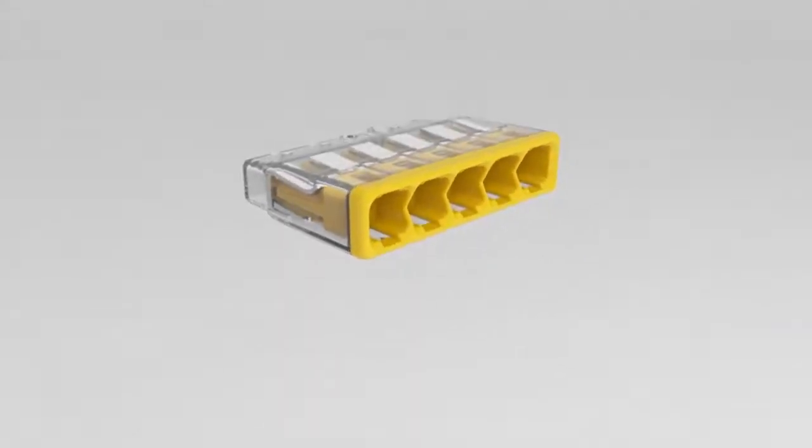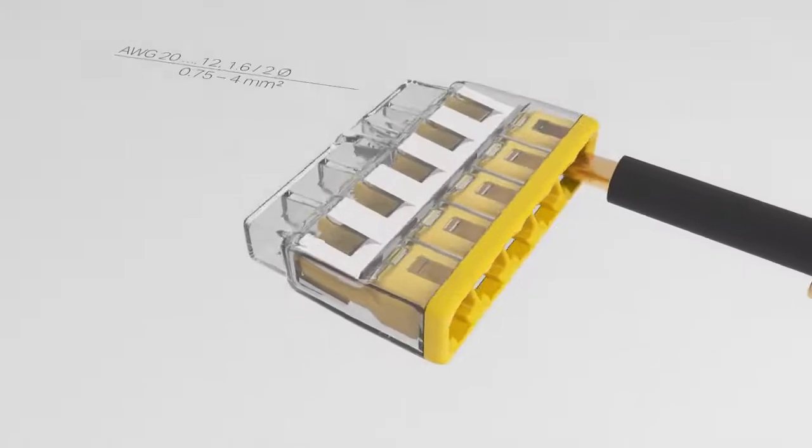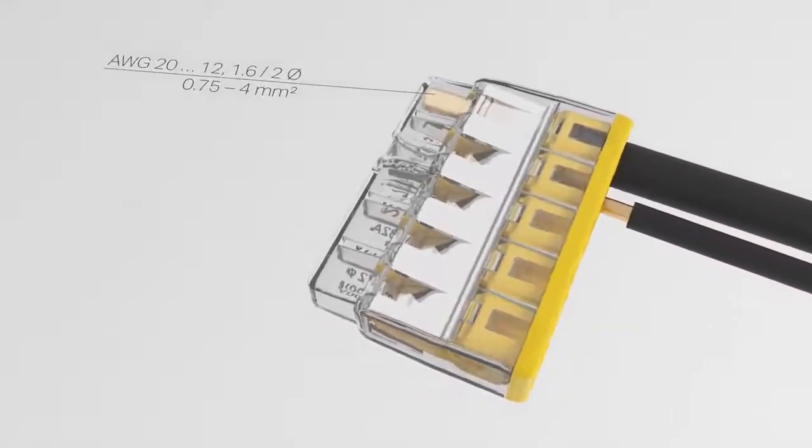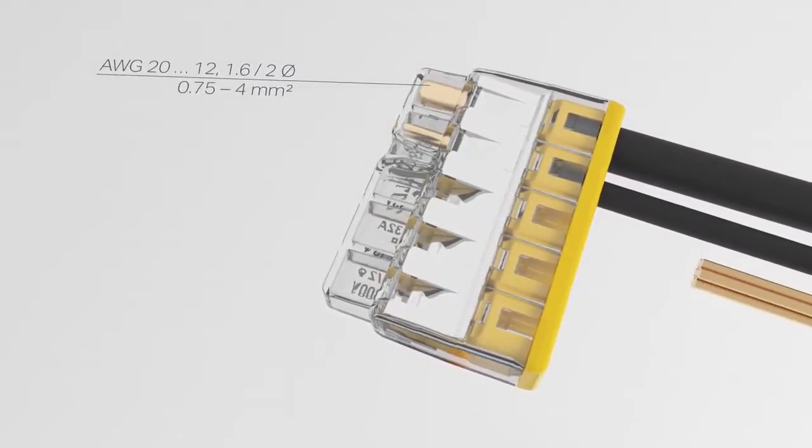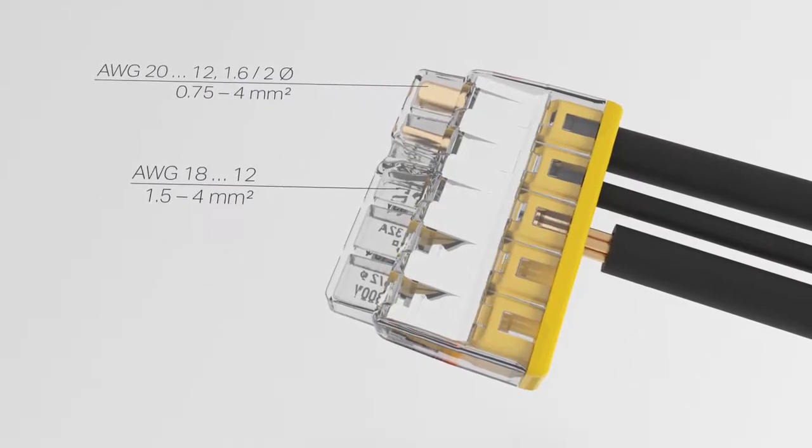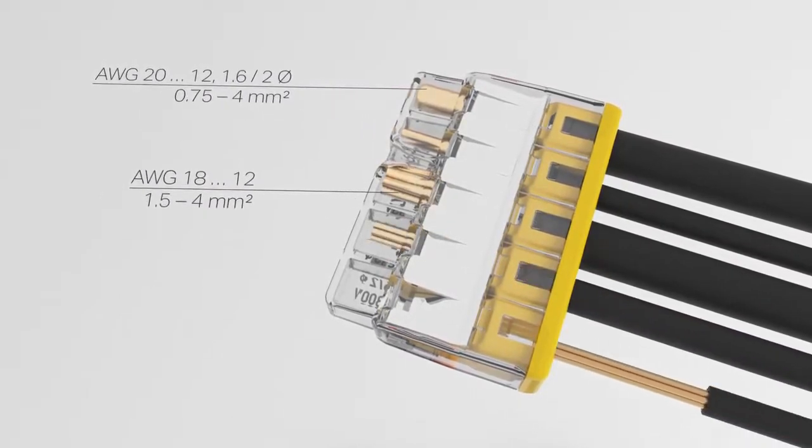Solid conductors with cross sections ranging from 0.75 square millimeters to four square millimeters and stranded conductors from 1.5 square millimeters to four square millimeters can be reliably connected just by pushing them in.